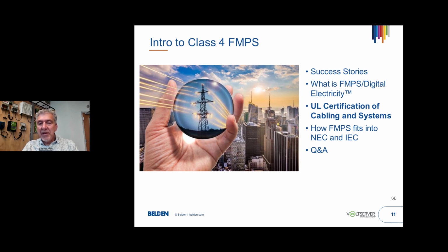We'll talk about some of the success stories we've had with fault managed power systems, noting that VoltServer was the originator of the technology class. But going forward, multiple vendors are starting to produce this equipment, so there will be multiple options to obtain fault managed power systems. Right now it's a single-source situation with VoltServer, but that will change quickly, particularly with the new UL standards and National Electric Code entries supporting the technology.